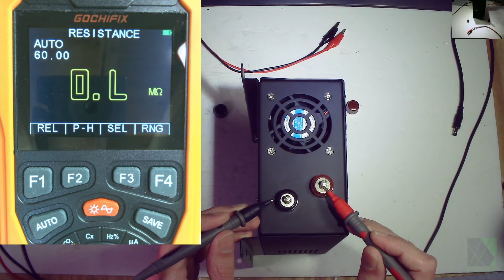It's not short circuit. And what are the different things that you might see if you do a test like this? Well, one would be an open circuit. If you probe the inverter, just like I did here, like I showed you, and you don't see anything on the meter. Now, I'm not actually touching the probes to the other terminal, but let's just pretend that I did, and you saw OL on the meter like that. What is that telling you? What that's telling you is there's an open circuit on the input of the inverter.